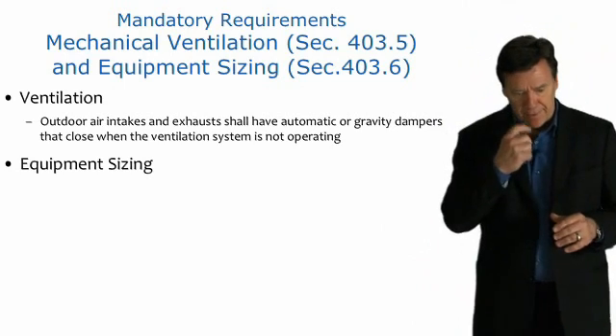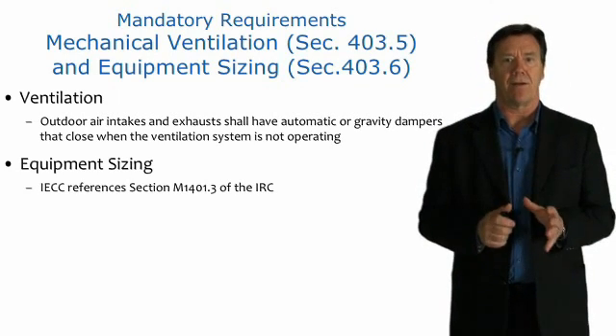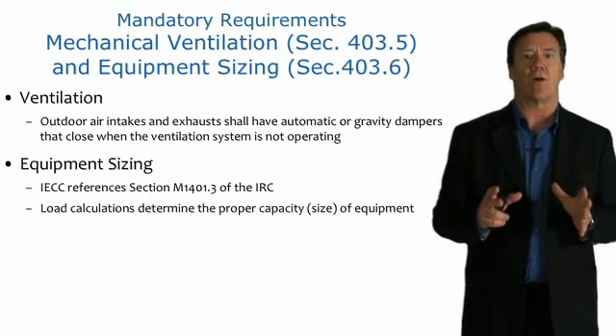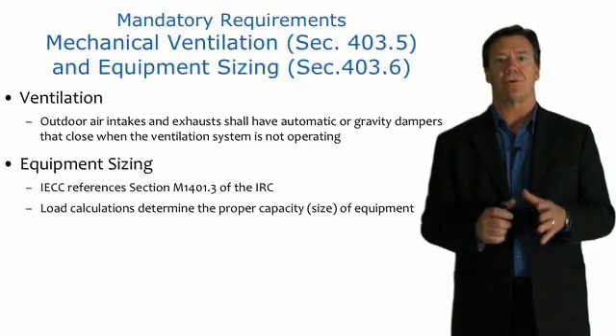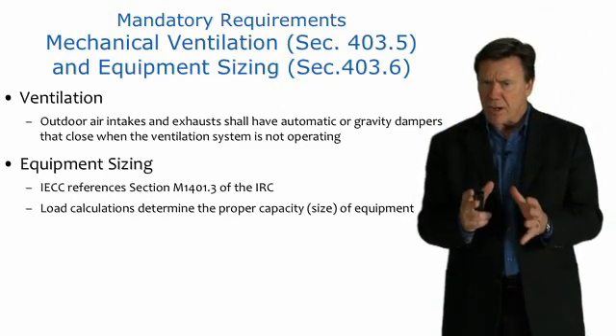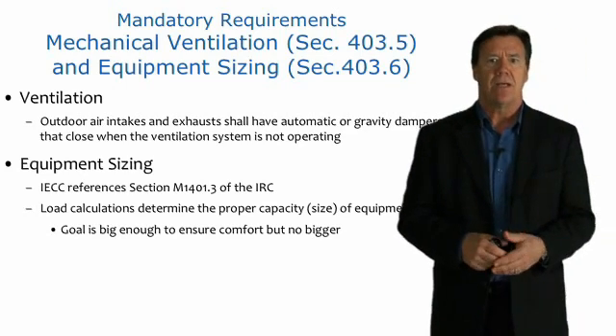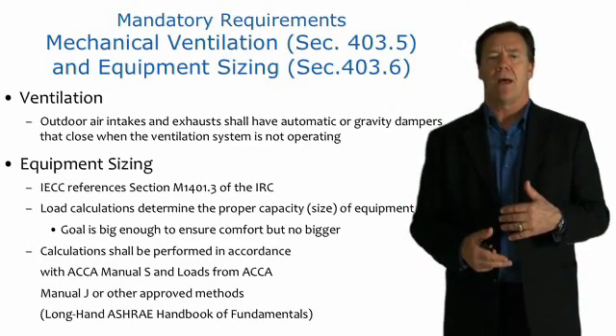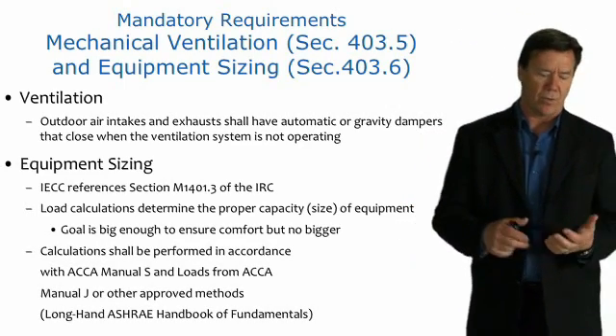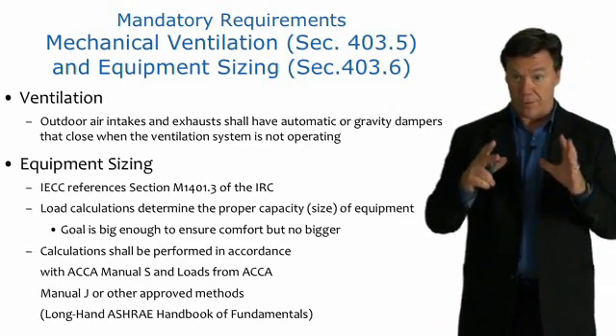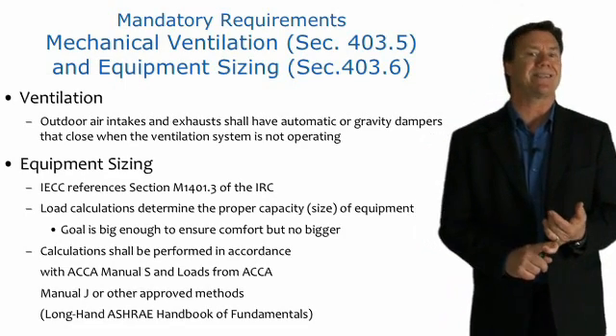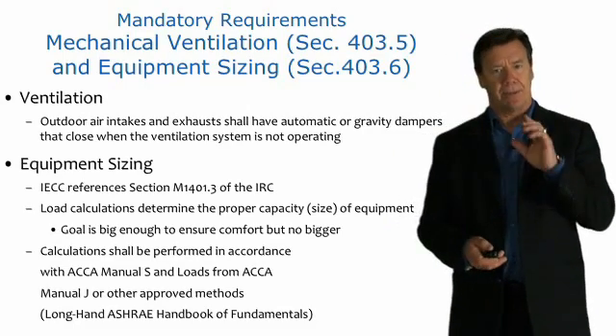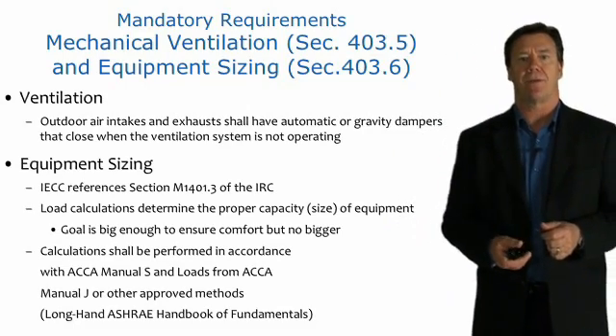Equipment sizing: the IECC refers to the mechanical code and requires that load calculations be done to ensure the building is comfortable but no larger than absolutely necessary. We use the Air Conditioning Contractors Association of America sizing protocols — Manual J to determine building loads, Manual S to select the equipment, and Manual D to design the ducts. This is a requirement within the code.